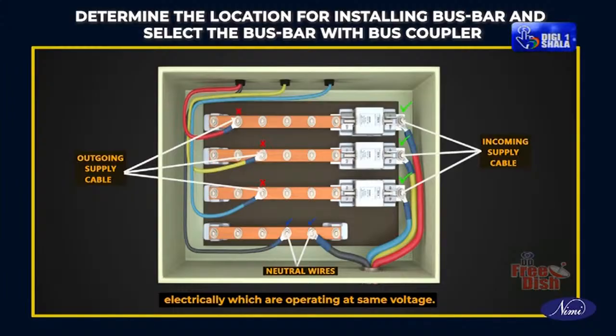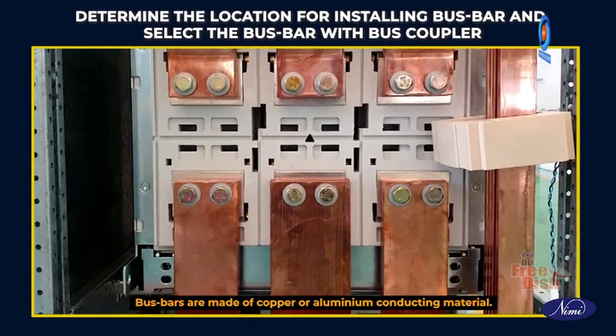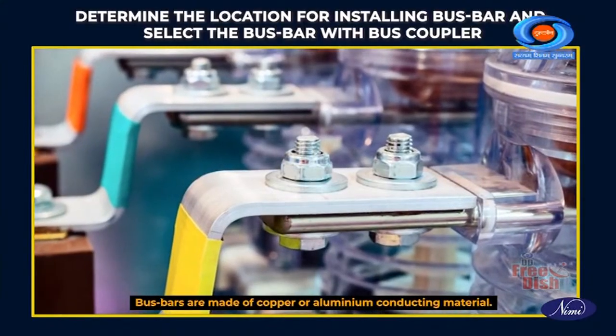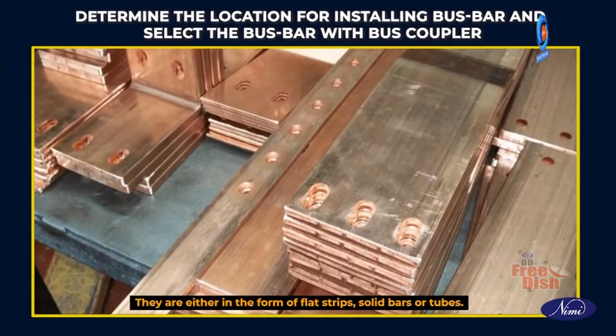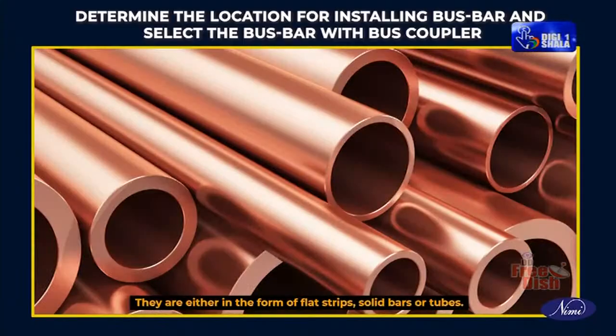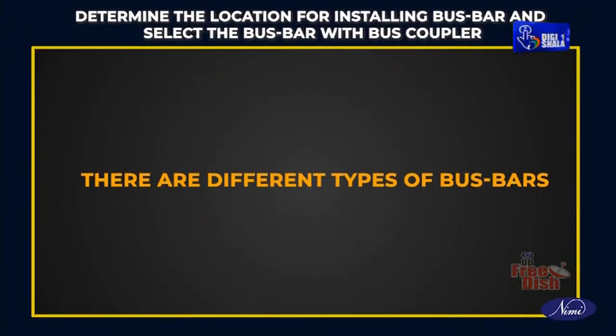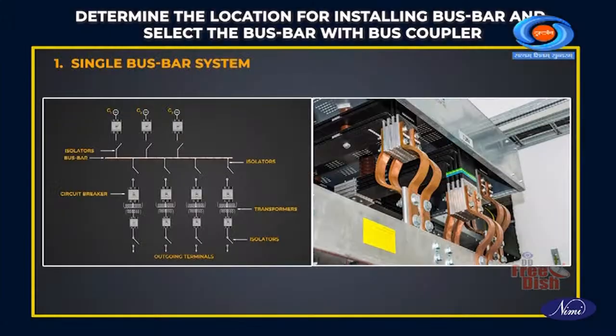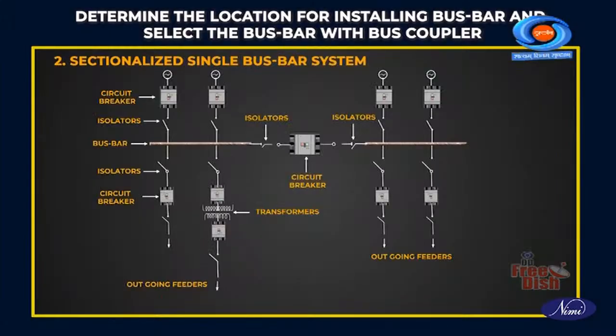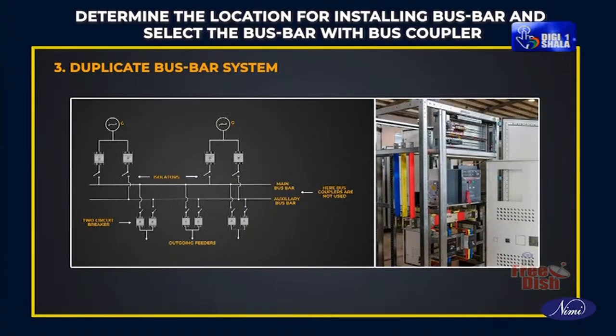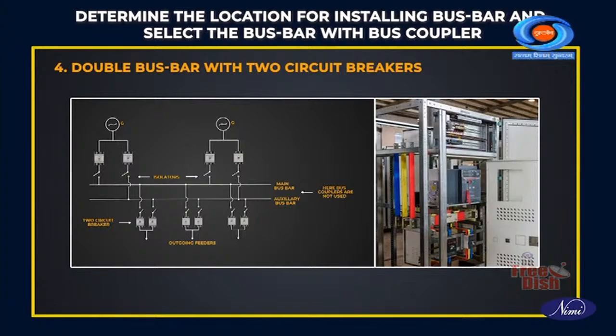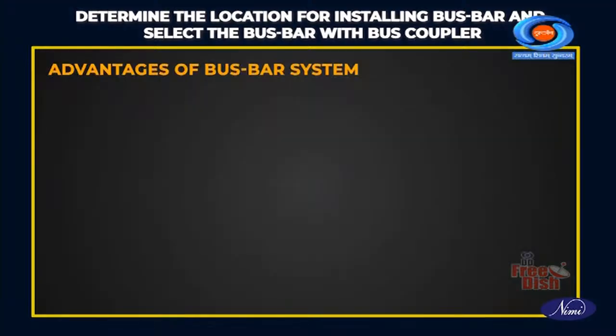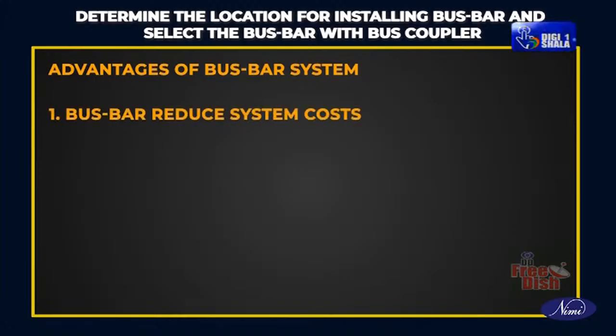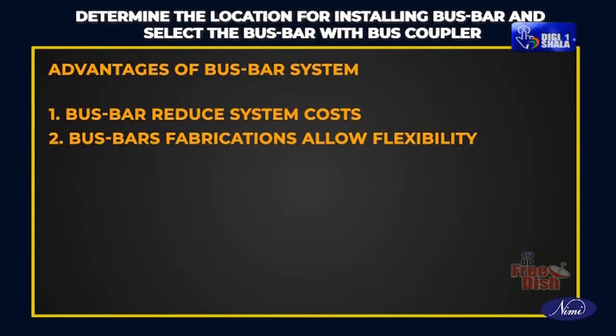operating at same voltage. Bus bars are made of copper or aluminium conducting material. They are either in the form of flat strips, solid bars, or tubes. There are different types of bus bars: single bus bar system, sectionized single bus bar system, duplicate bus bar system, double bus bar with 2 circuit breakers. Advantages of bus bar system: bus bar reduce system costs. Bus bars fabrications allow flexibility.